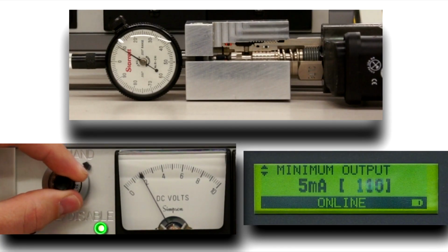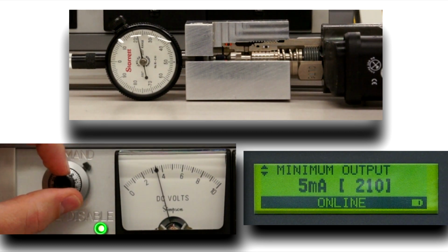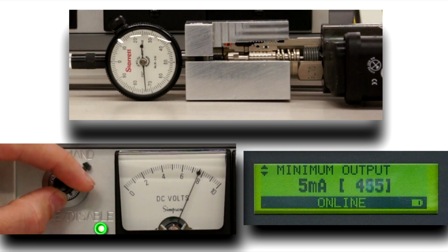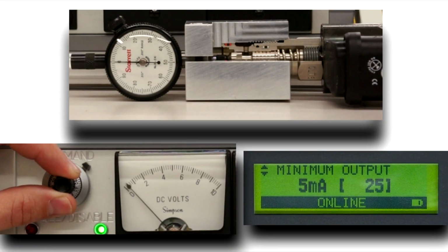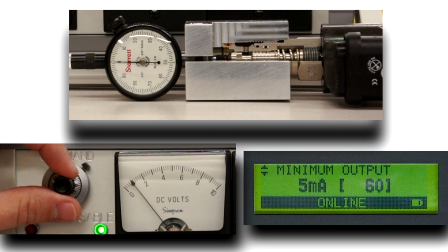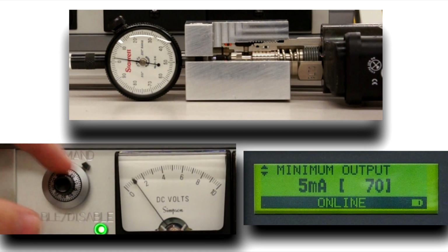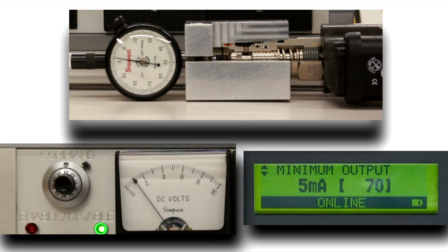One thing you may notice here is that when I started giving it an input command, there was no valve movement for a given amount of input. This is called deadband. If I very slowly increase the command voltage, you'll see the output current increasing but no valve position change. As you keep ramping up the input, there will be a certain point where the valve will begin to move. What you will see is it took about 70 milliamps to make the valve move.